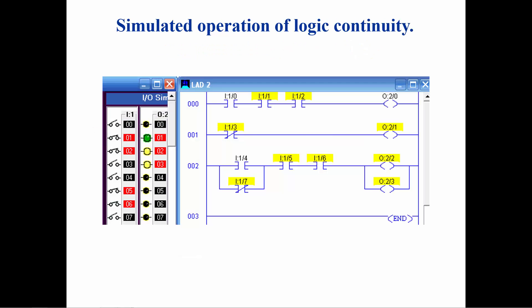In this simulation you will see multiple variations of the use of the examine if closed and the examine if open instructions. Eight different input switches are being used by the instructions. Rung 0 will only have logic continuity to the output instruction when all three of the switches addressed by the examine if closed contacts are closed. The yellow highlighting indicates logic continuity through the instruction. Rung 1 only has an examine if open contact; in order to have logic continuity, the instruction needs to be true, which occurs when the switch at I colon 1 slash 3 is open.